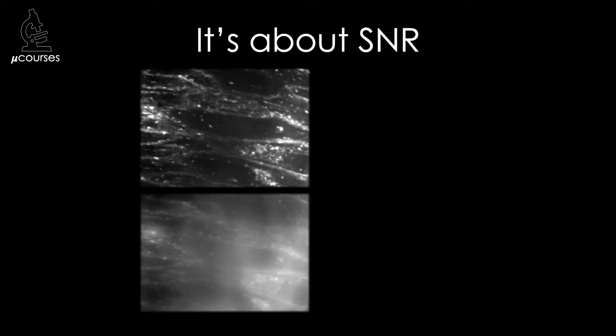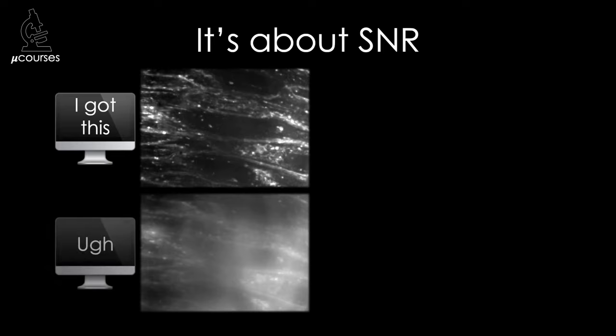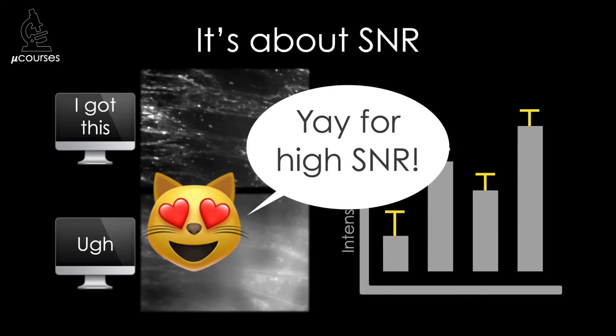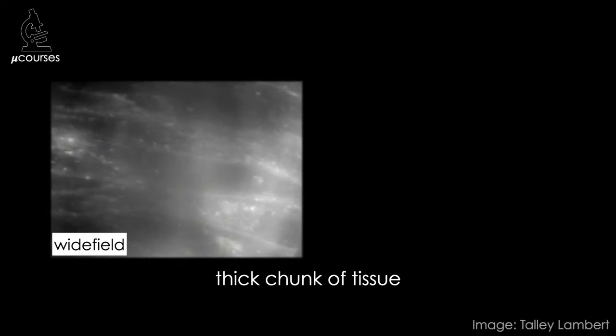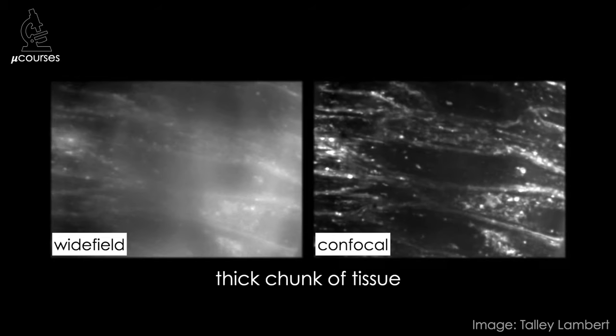Why is signal-to-noise ratio important? High signal-to-noise ratio images are generally easier to segment for image analysis, and will result in more precise measurements of intensity values and less error. Some biological specimens contain lots of out-of-focus fluorescence, and confocal microscopes can be used to increase the signal-to-noise ratio of images of these types of specimens.